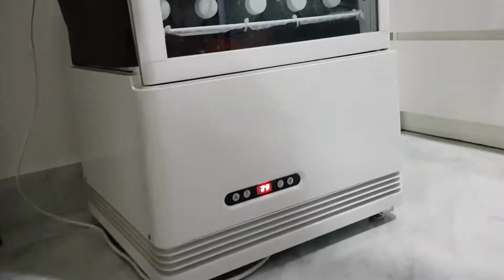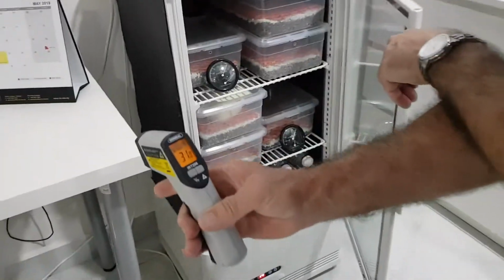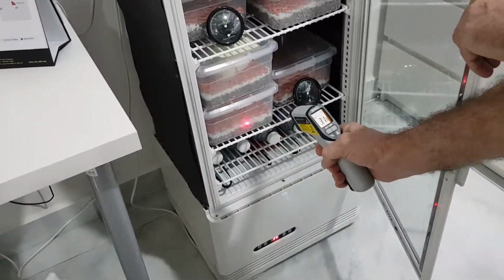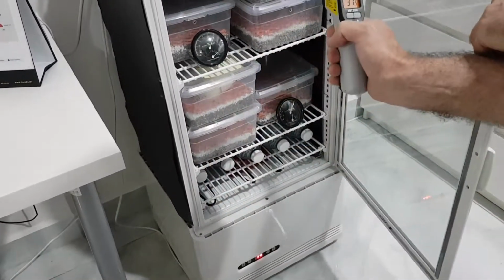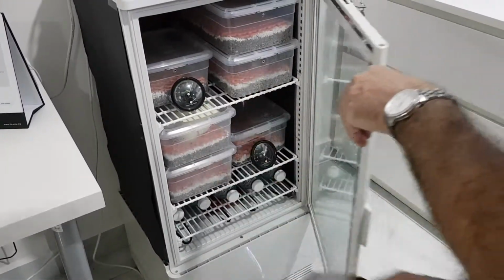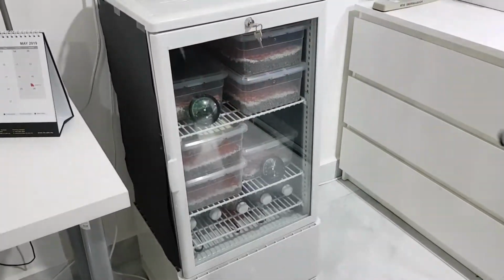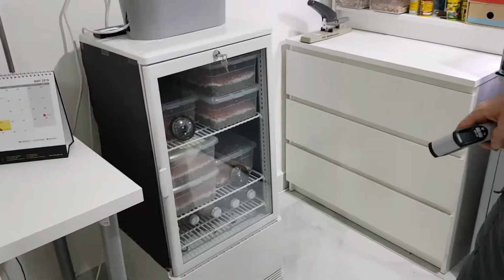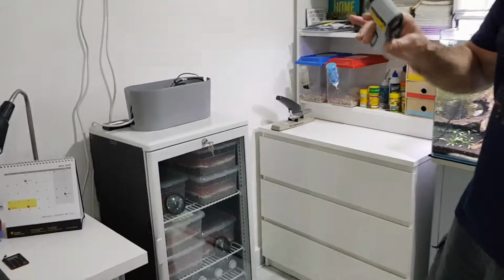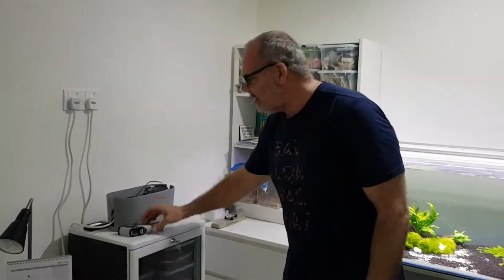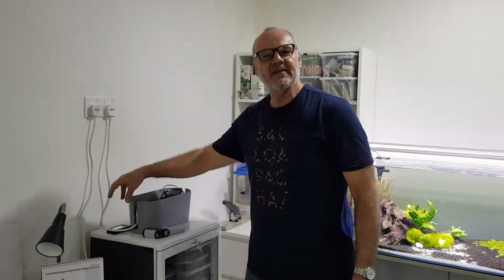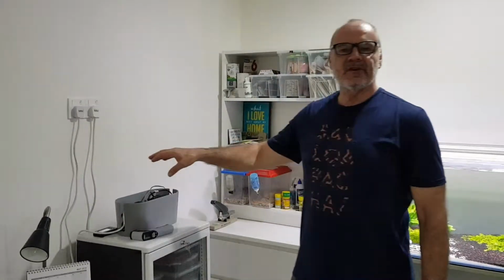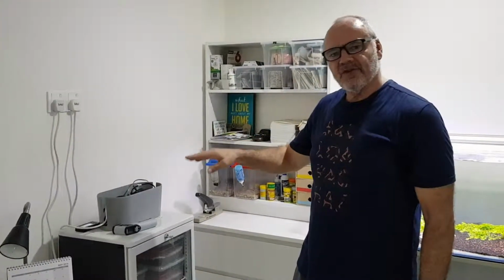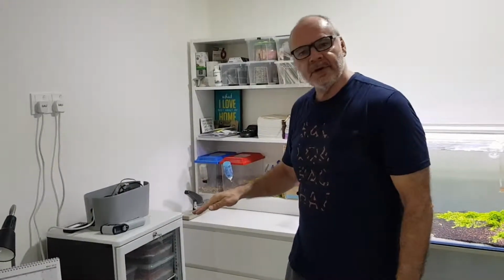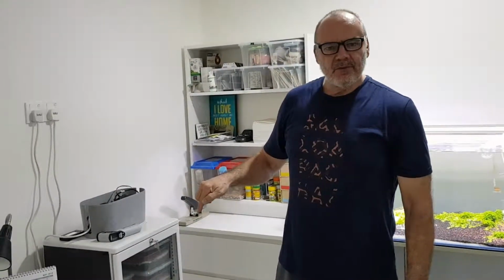But if I actually use the heat gun inside the incubator, you'll see that that is 31 degrees, 31.5, 31.5. So the temperature in here is a nice 88.5, 89 degrees Fahrenheit for those that work in Fahrenheit, 31.5, 31.6 for those that work in centigrade, despite the fact that this thermostat is set for 29.5. That's the temperature I need to set it at in order for it to switch off before it overheats and to switch on before it gets too cool.